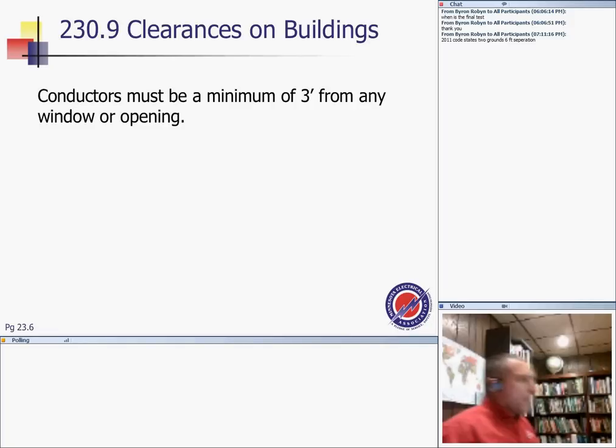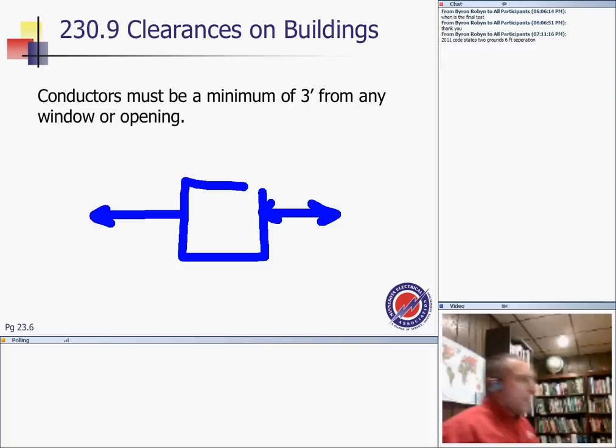Of buildings, conductors must be a minimum of 3 feet from windows or openings, and they can't be below. They have to be to the side. And we all know if you have a window, they can be to the side here, 3 feet, clearing it all the way up to 3 feet. 3 feet when you put your power lines. Clear it of your power lines.